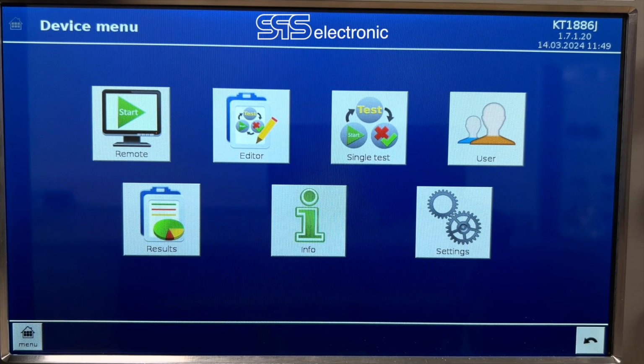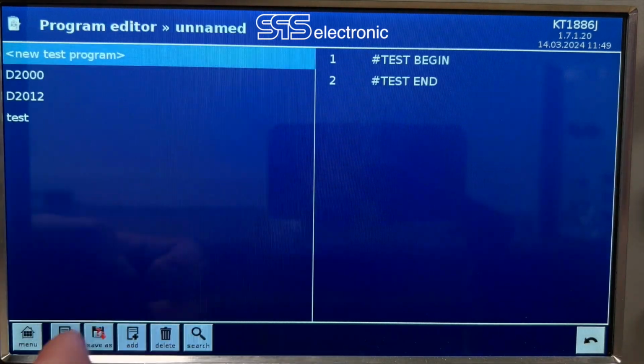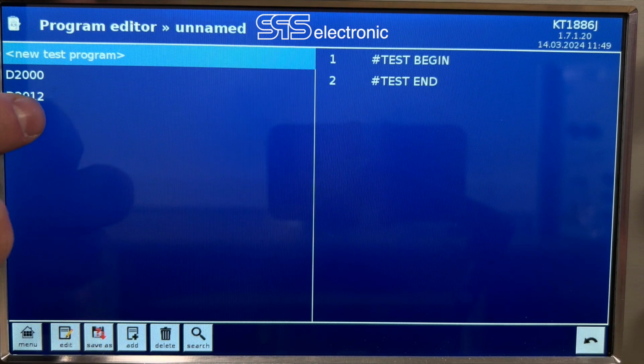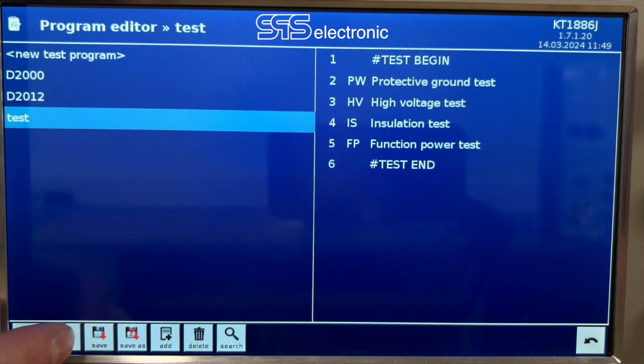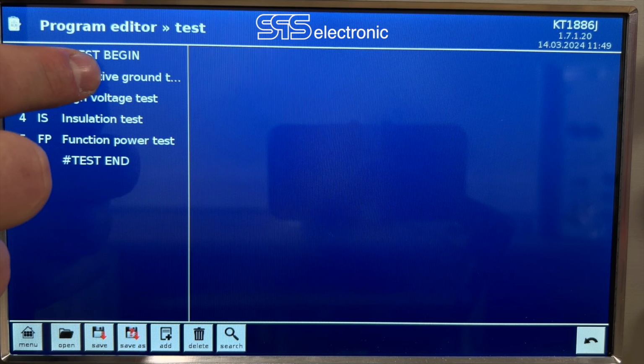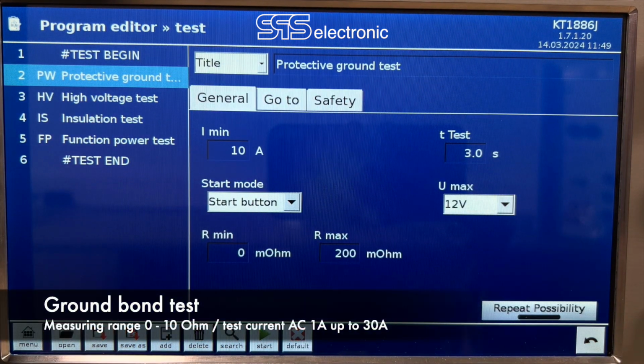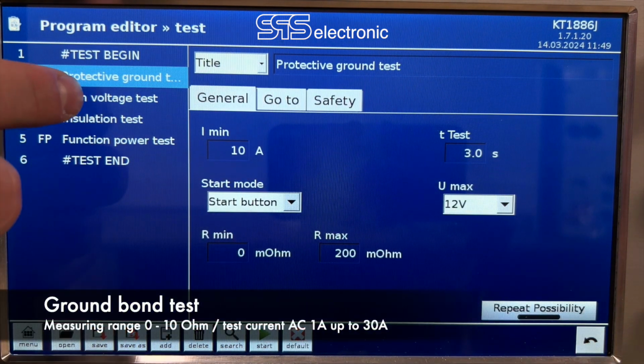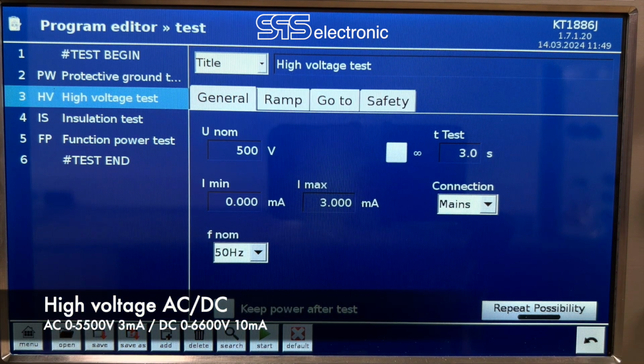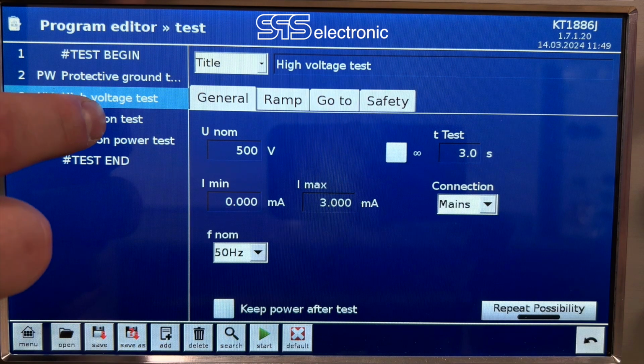In menu, you will press editor. Here you can choose a new test program or existing one. I already prepared the test program of our test, so let's take a look. The first one is protective ground test, where you will set up current, test time, and minimum and maximum resistance. The next one is high voltage, where we'll also set up voltage, test time, and current.